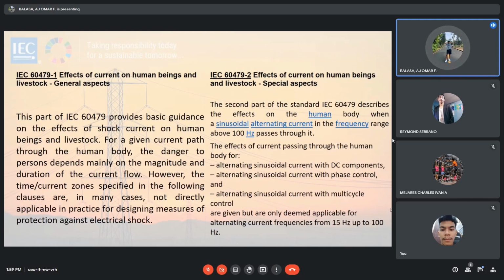IEC 60479, effects of current on human beings and livestock, general aspects. This part provides basic guidance on the effect of shock current on human beings and livestock for the given current path through the human body. The danger to persons depends mainly on the magnitude and duration of the current flow. However, the time-current zones specified in the following clauses are in many cases not directly applicable in practice for designing measures of protection against electric shock.